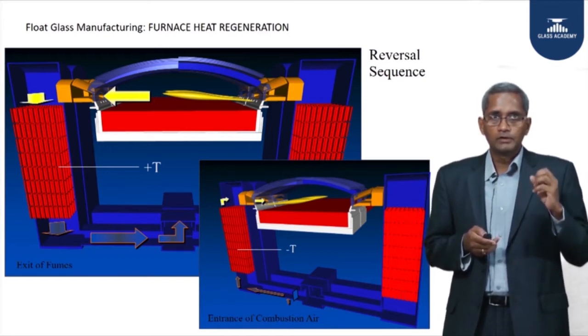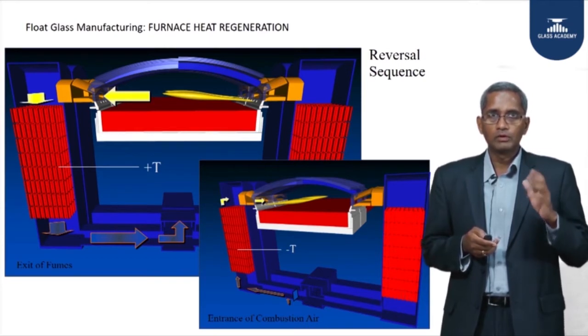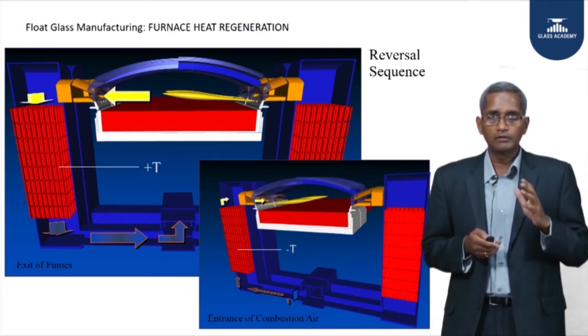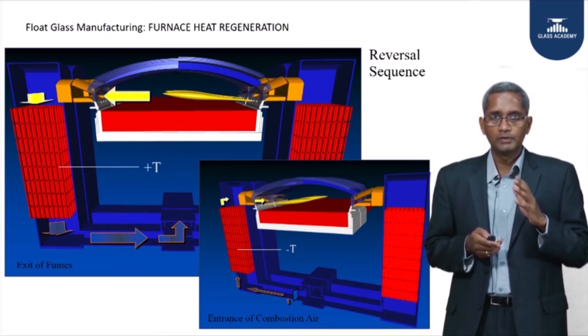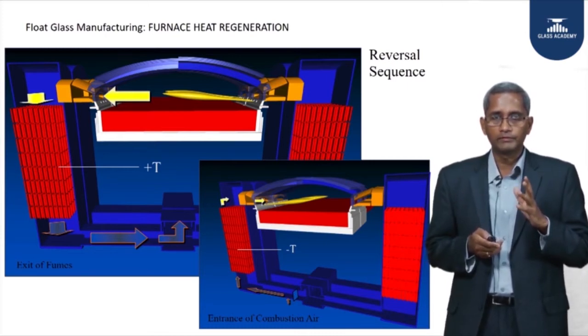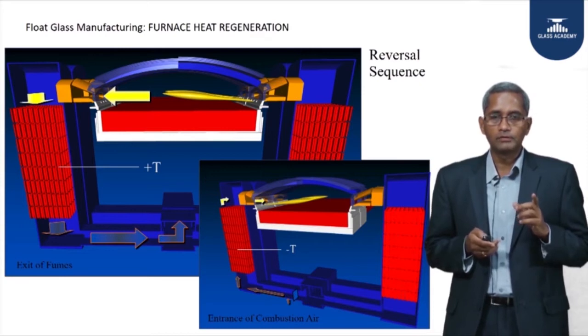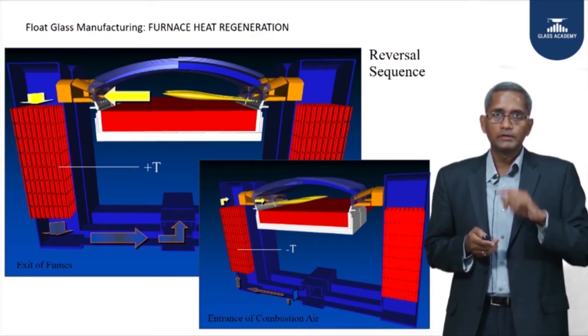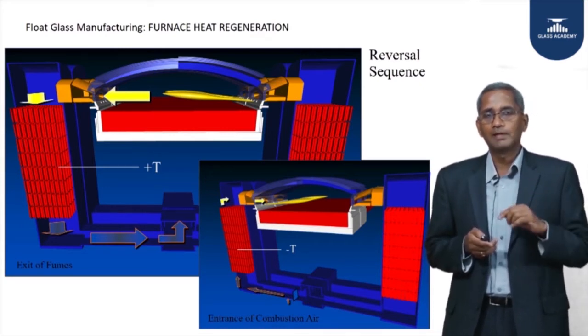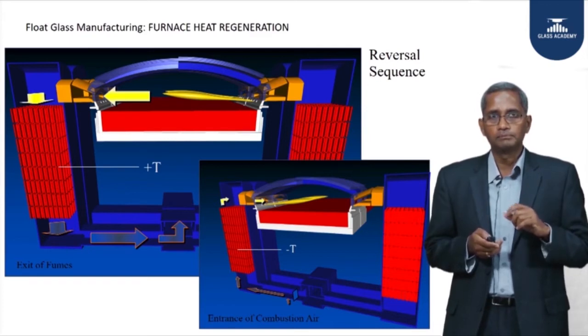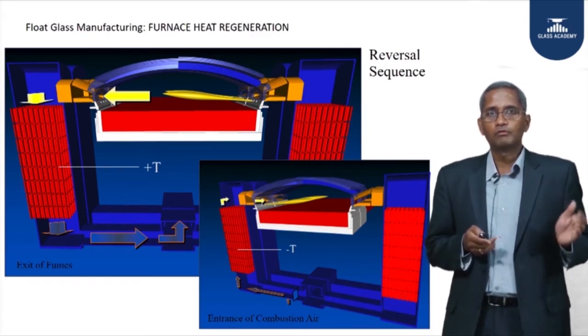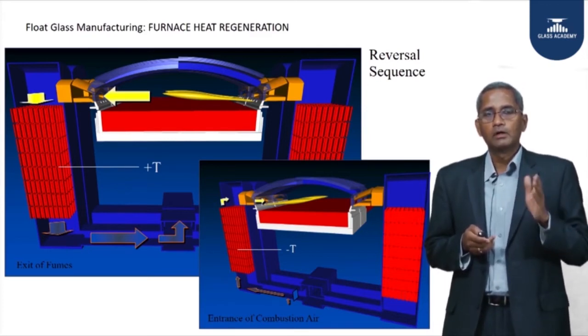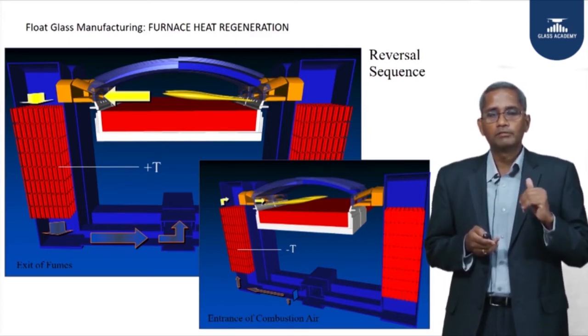After 20 minutes, the regenerator is now more or less full with heat. At this point we stop the fuel and the combustion air on the right hand side, and change the equipment such that combustion now starts from the left hand side — meaning the fuel oil and combustion air are coming from the left hand side.